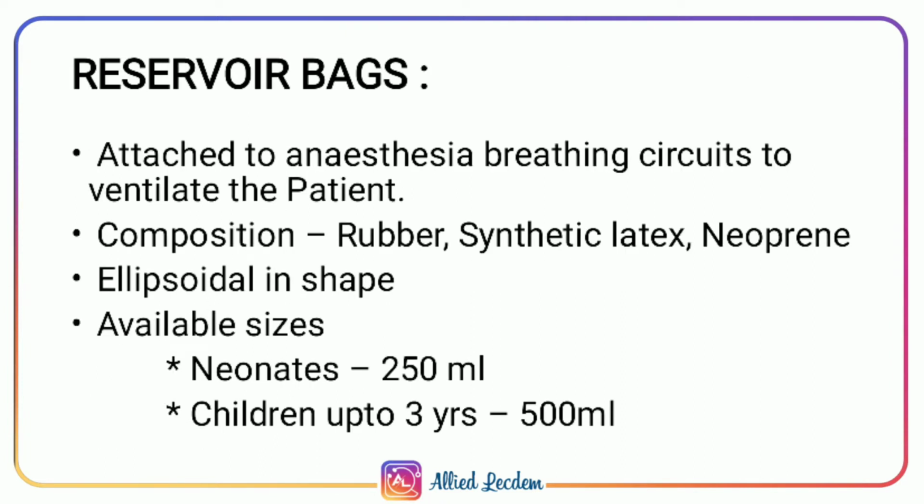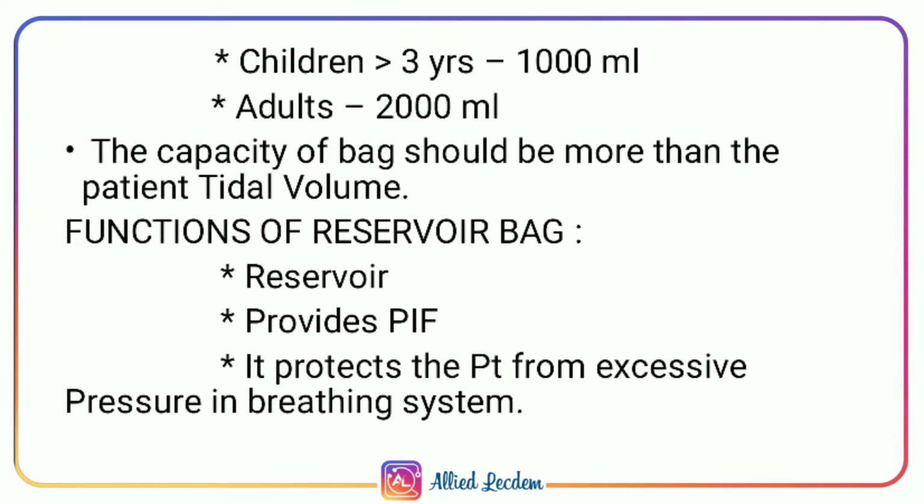Reservoir bags, otherwise called breathing bags, are made up of rubber or synthetic latex. They are connected to the anesthesia breathing circuit to ventilate the patient. Bags with different capacities are available for various age groups. For neonates, we use 250 ml. Children up to 3 years, we use 500 ml. Children above the age of 3, 1000 ml. For adults, it's 2000 ml.